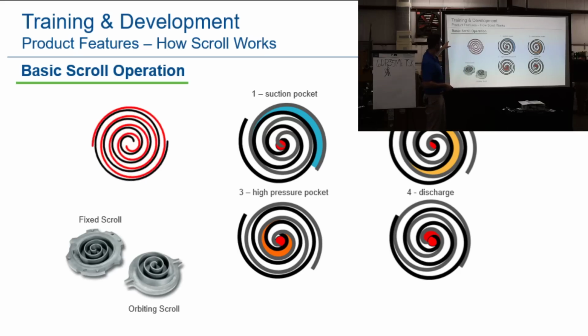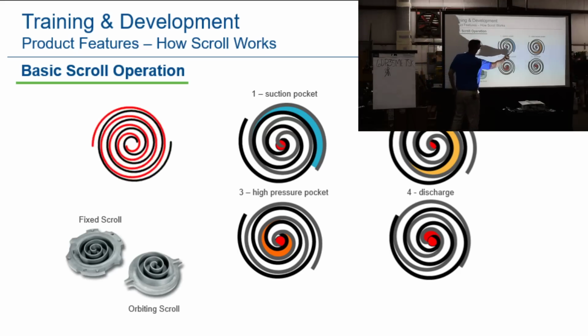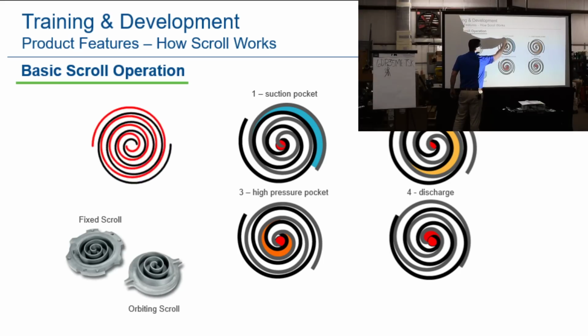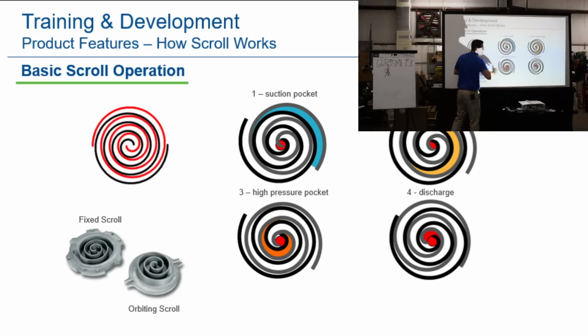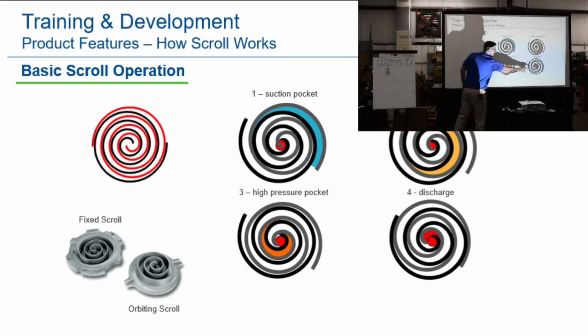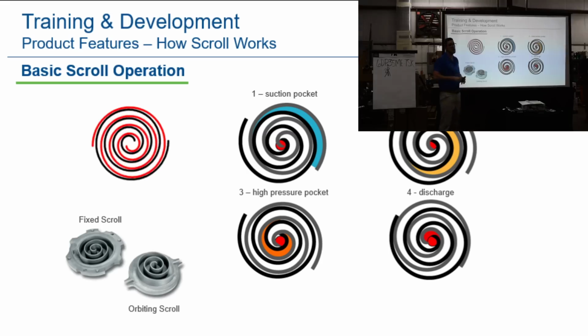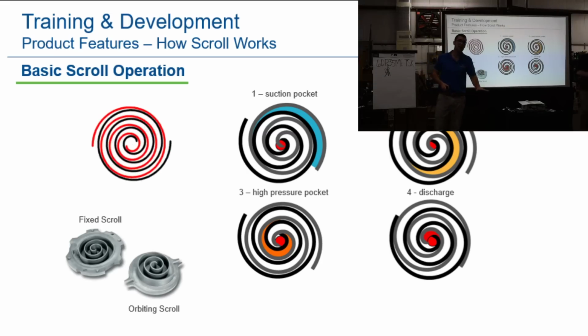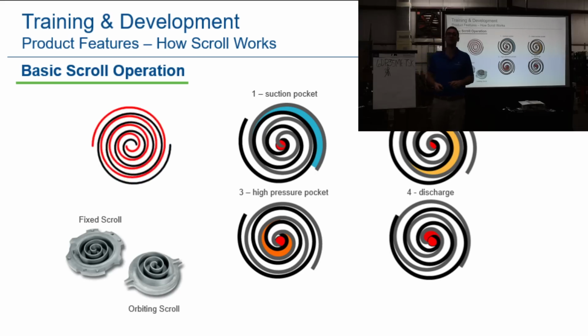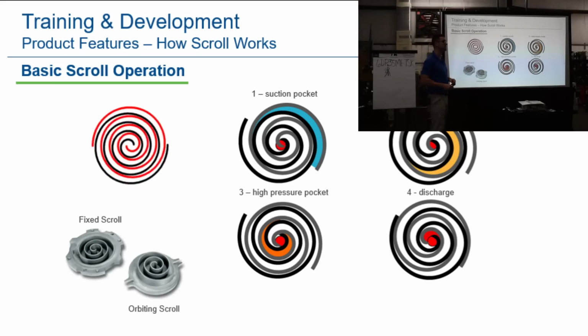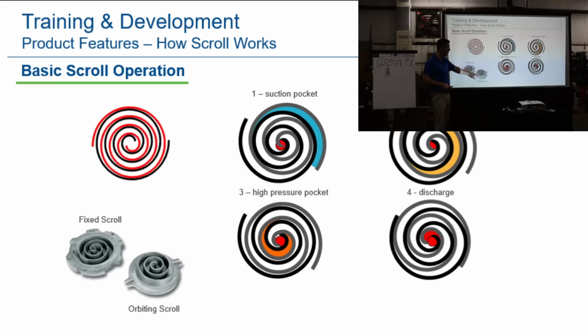How a scroll works: a continuous pumping action. As the scroll pockets work, you've got suction coming in, it squishes that gas and compresses it until it goes out at the top. The top is the discharge. So if you put your hand on a scroll, it's going to be hot. You're going to be like, that's pretty hot, depending on the application again. Thank you. Pass that around. That's great. So you have a fixed scroll set on the top and an orbiting one on the bottom.